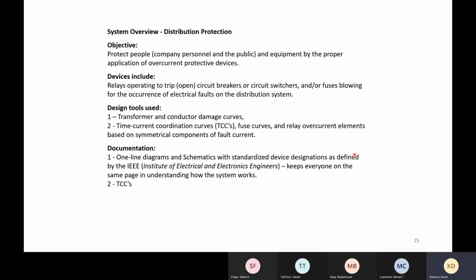a typical breaker is anywhere between, depending on the vintage, a modern gas breaker, I've seen a lot of them operate at about 2.5 cycles, even though they're listed at 3, and you can go all the way back to old oil circuit breakers, and some of them are as slow as 10 cycles. So if you have someone with 1,000 amps flowing through them for that long, chances are they may not make it anyway. So I always caveat the protecting people part. We do the best we can, but there's no guarantee that if somebody comes in contact with a live circuit, the breaker operating time alone can be enough to save them.